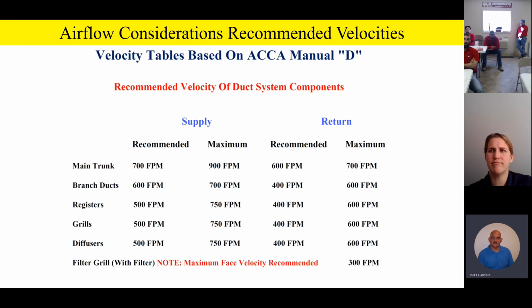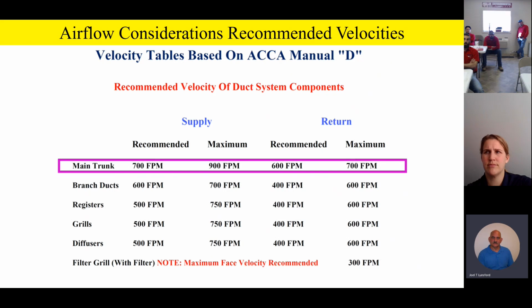In addition, don't forget Manual D, which is our ACCA Manual D, our airflow and duct design criteria when we build a duct system. This table right here is right out of Manual D, and it's recommended duct velocities as well. So you not only have to have the right CFM, but make sure that your air is not moving too fast down your ductwork or your takeoffs. These are just some examples, like your main trunk or your home run. You're going to want to have somewhere between 700 and 900, maximum 900, feet per minute velocity down that main trunk.